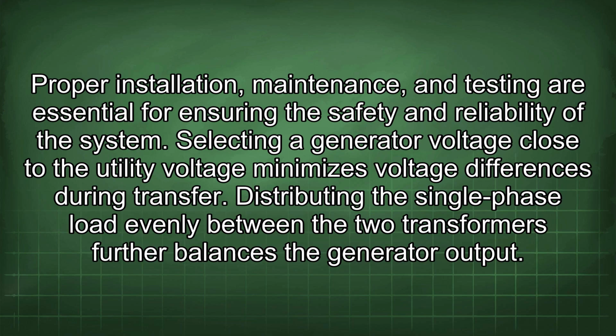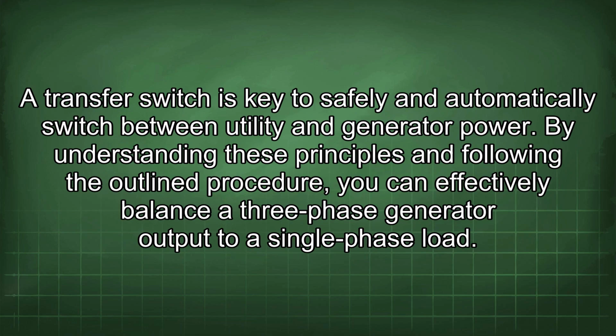Selecting a generator voltage close to the utility voltage minimizes voltage differences during transfer. Distributing the single-phase load evenly between the two transformers further balances the generator output. A transfer switch is key to safely and automatically switch between utility and generator power. By understanding these principles and following the outlined procedure, you can effectively balance a three-phase generator output to a single-phase load.